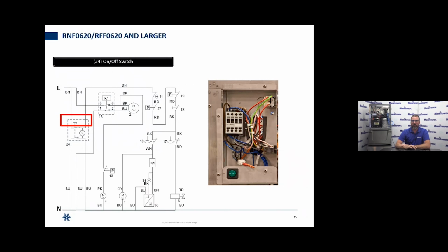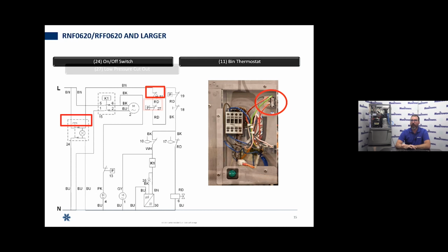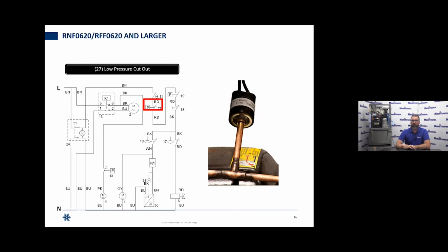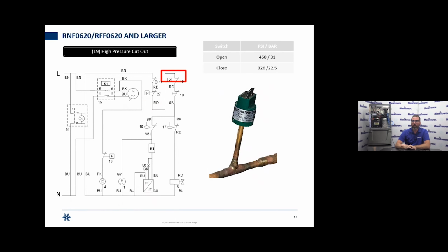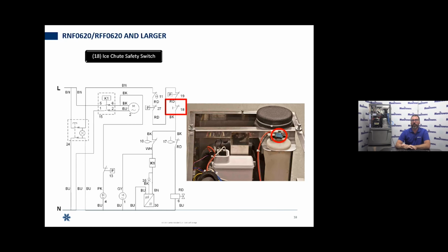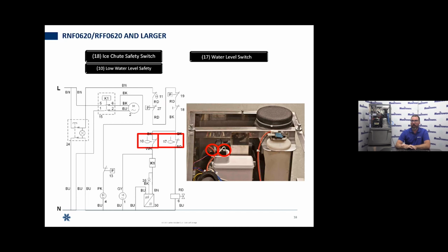So we'll take a look at some of these components and how they look in the wiring diagram. Of course, we have our on-off switch, and the bin thermostat that controls the level in our storage bin. Our low pressure cutout on this particular unit: if we start running into low suction pressures, we're going to cut that cutout switch and that will, of course, shut the machine down. High pressure cutout, just like we saw earlier. Ice chute safety switch, nothing new there.